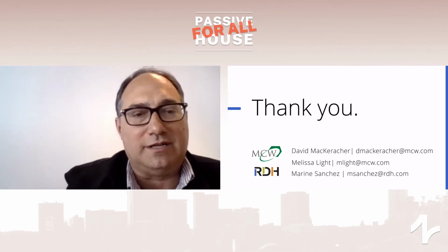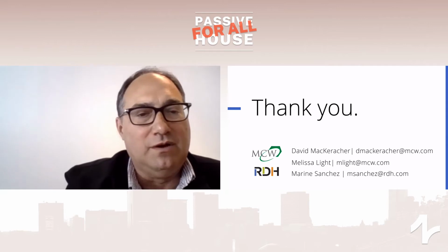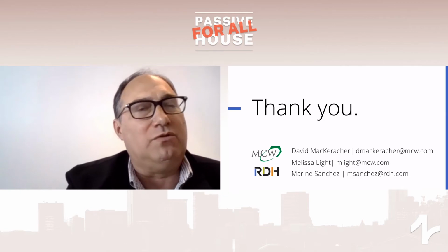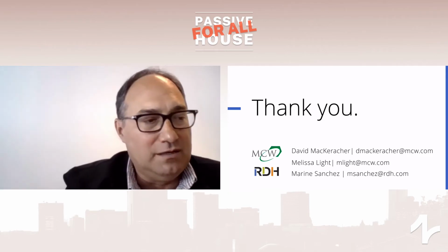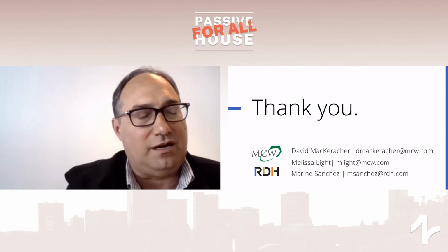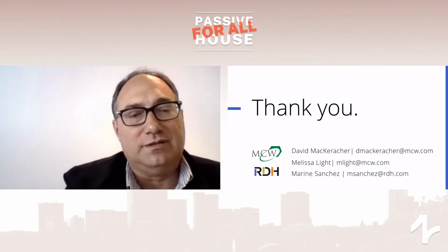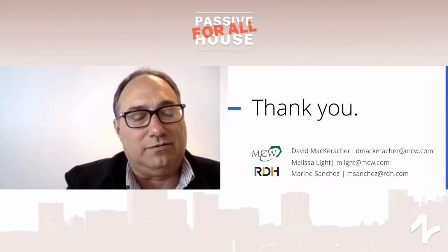And the problems that we've had in some of our decarbonization projects in existing buildings that have been using 160, 180 degree Fahrenheit water to heat their building, now we are limited with 130 degree water off the heat pump as typically the highest temperature that we can get. It is how we go about either supplementing that 130 degree water with additional heating during the highest heating periods, either with electric boilers where the existing infrastructure cannot accommodate that lower temperature, or in some cases we have actually gone in and we have changed air handling unit coils to bigger surface area coils that can accommodate the lower grade or the lower temperature waters.